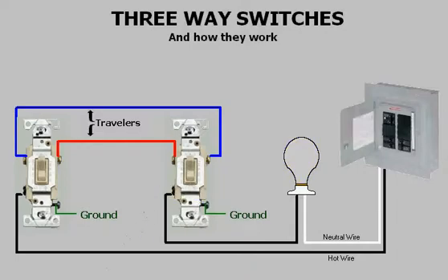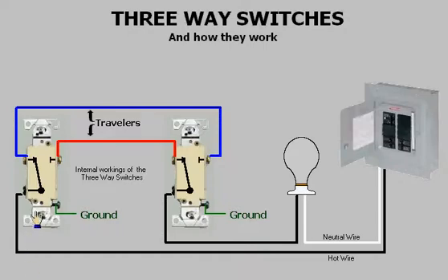If you look inside a three-way, you will see that it is a single pole, double throw switch. When you switch a three-way, it breaks with one contact and it makes with the other.